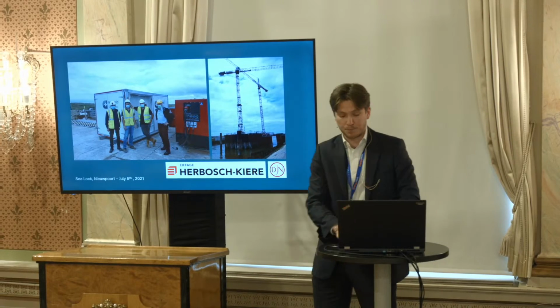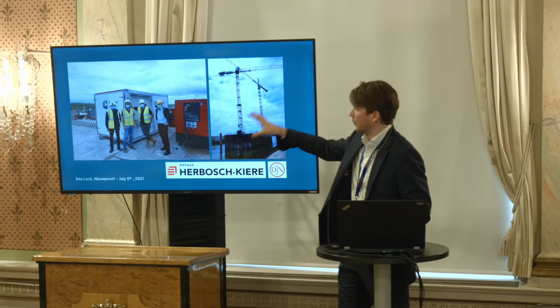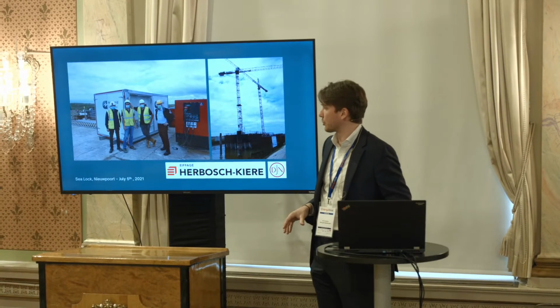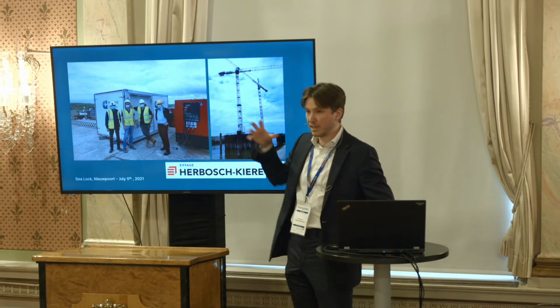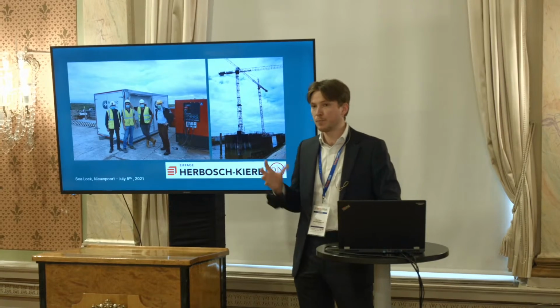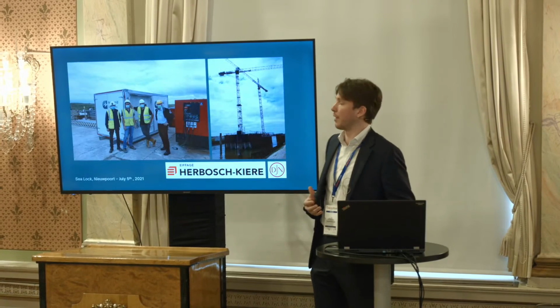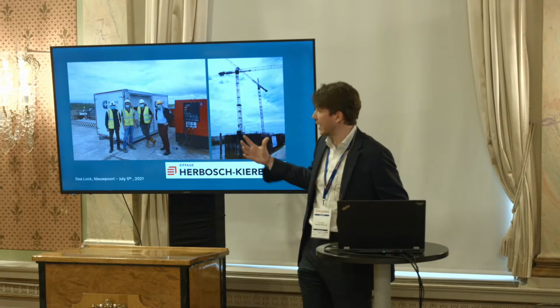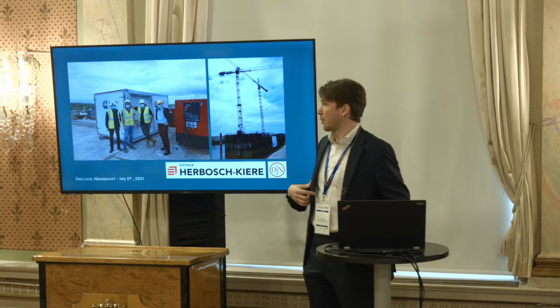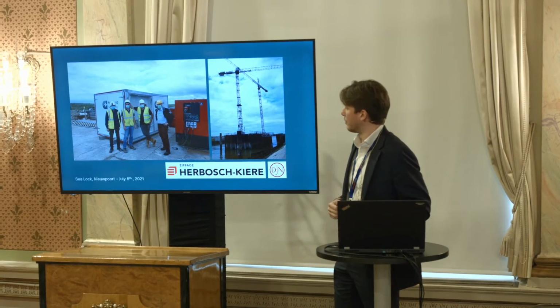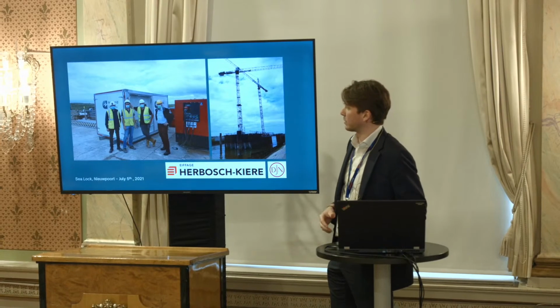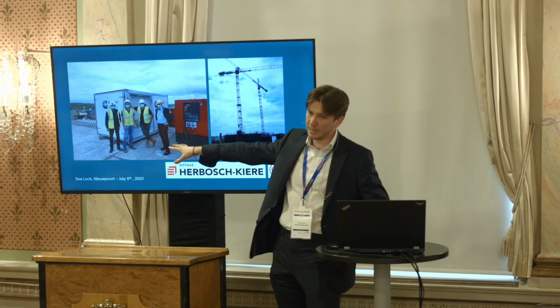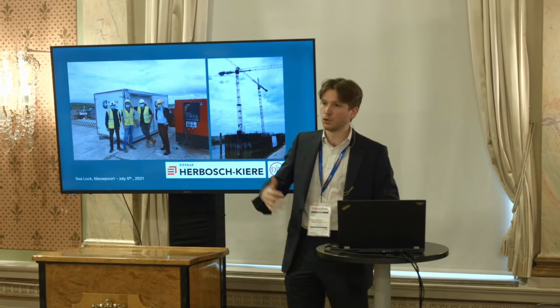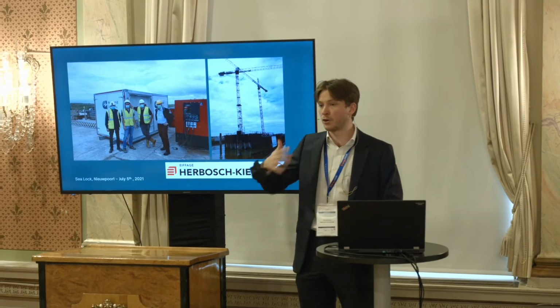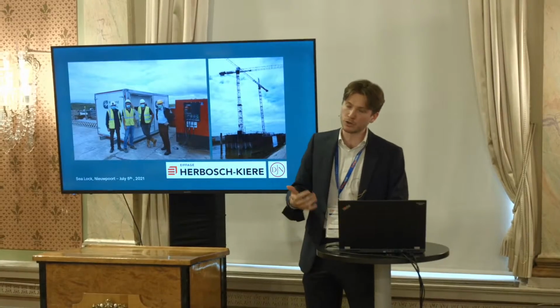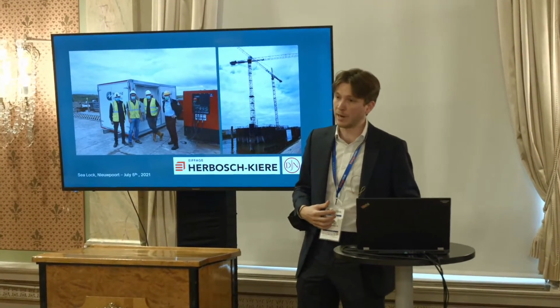Here we have a special situation in which we created a hybrid solution. We have a smaller diesel generator of 60 kVA, making actually the grid for our battery, and then we leverage the power to feed 2 big tower cranes on one site. If we weren't there on that construction site, 2 big diesel generators of 150 kVA each would be used to power the tower cranes.